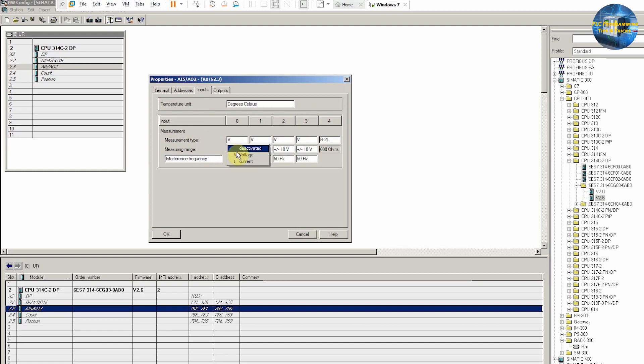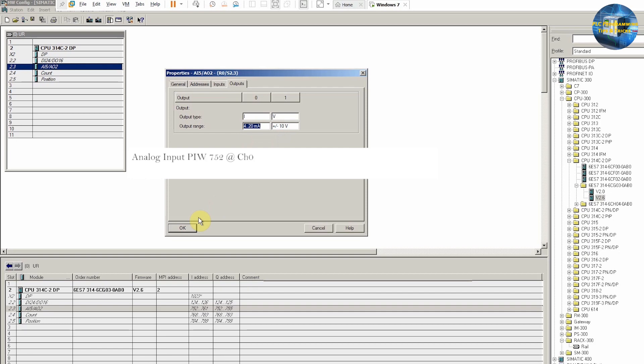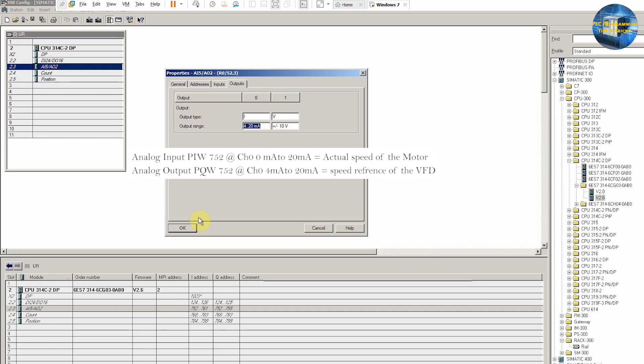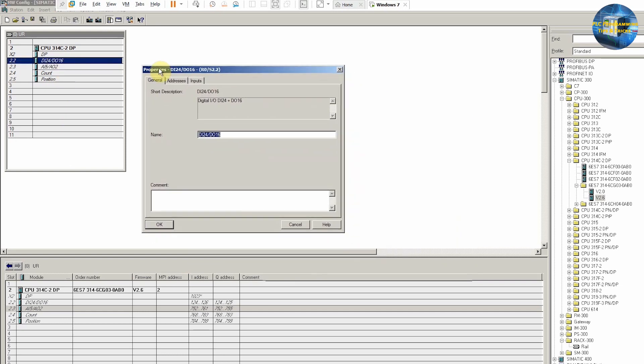We will open the analog I/O settings by double-clicking. We will set channel 0 of the analog input as a current input and set the signal range as 0 to 20 mA, since the analog signal coming from the VFD is also 0 to 20 mA. Next we will set channel 0 for the analog output as current and set its range as 4 to 20 mA. So we have analog input PIW752 with 0–20 mA range receiving the actual output frequency from the VFD, and analog output PQW752 with 4–20 mA range sending the speed reference signal to the VFD.